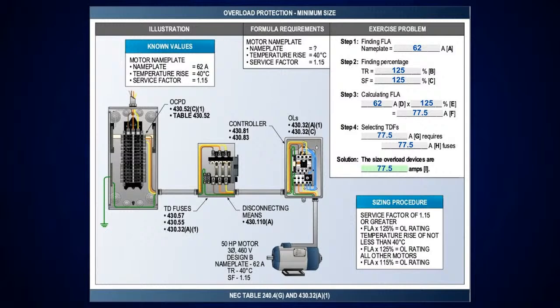told you is go look at 430.6(A)(2), and it tells you when you're doing your overload protection to use the nameplate value. Now there's three items I need to look at here. I don't even really care what size motor it is or what voltage it is. I want to know the nameplate, I want to know the temperature rise, and I want to know the service factor. That's it.